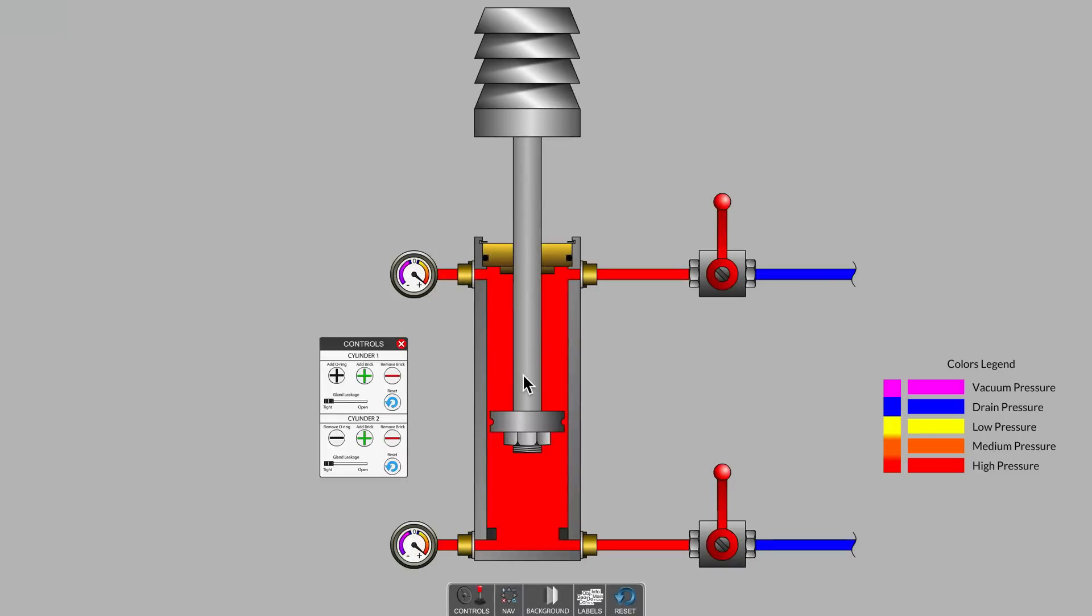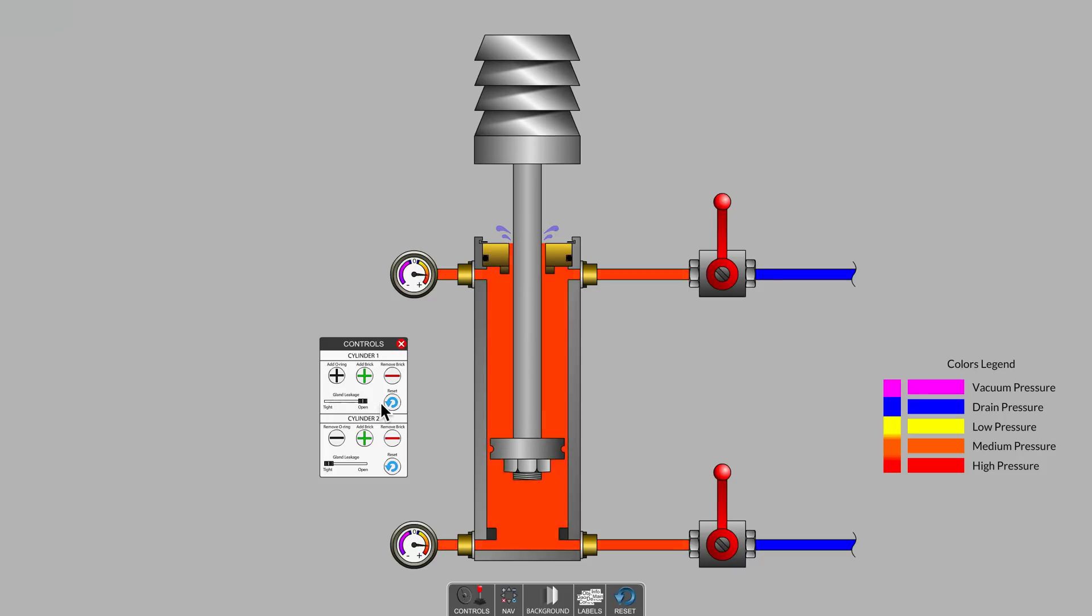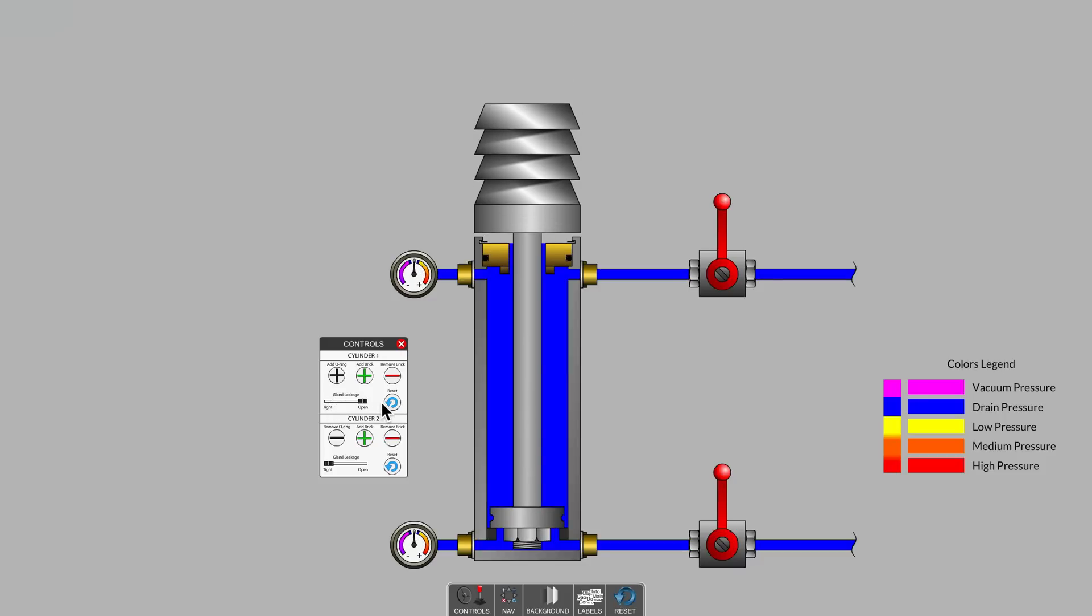Would the rod hold this position with the piston seal removed if the rod end gland bushing also became leaky? Of course not. With an easy path for fluid to exit the cylinder tube, space is made available for the full rod length.